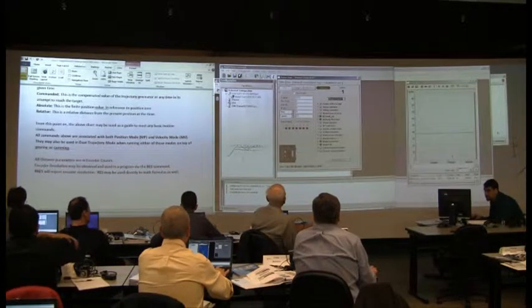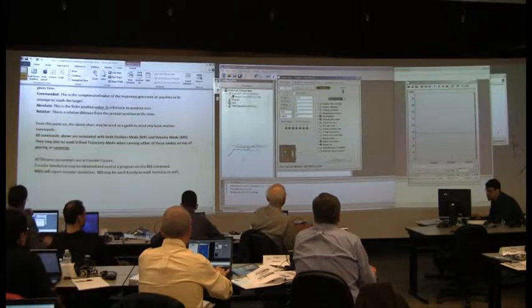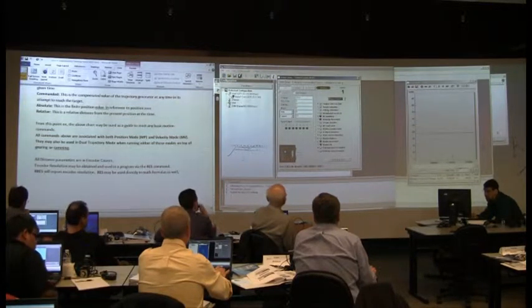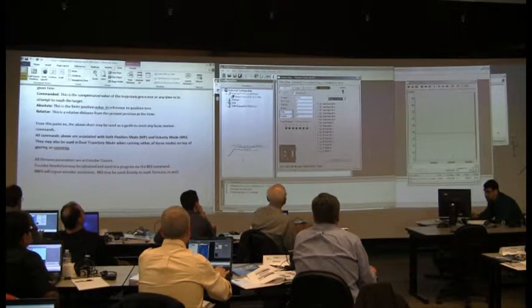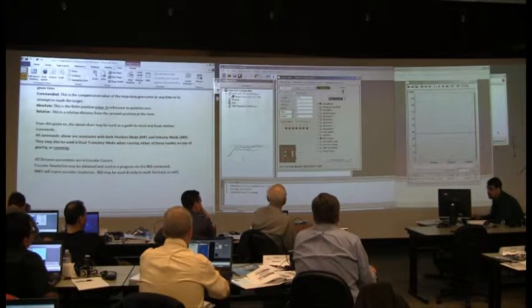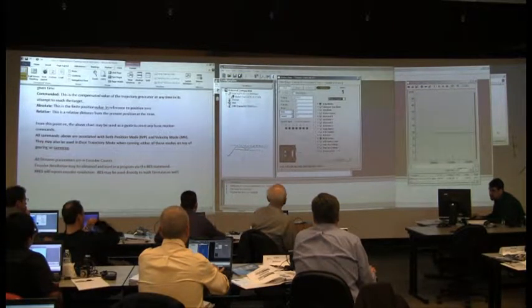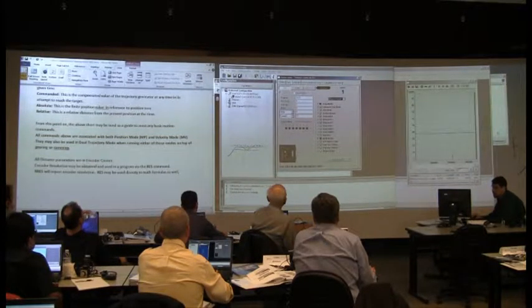Here's bus voltage saturation. That's a little bit different. That's actually when you're going at 100% torque and you got back EMF saturation. I can't remember what the other one is. There we go. Status word 6, low bus voltage, high bus voltage. Low is set at 8 volts, high is at 72. That's one of the ones that tell you which one it is. Okay? Hardware-wise, that's where you find them.